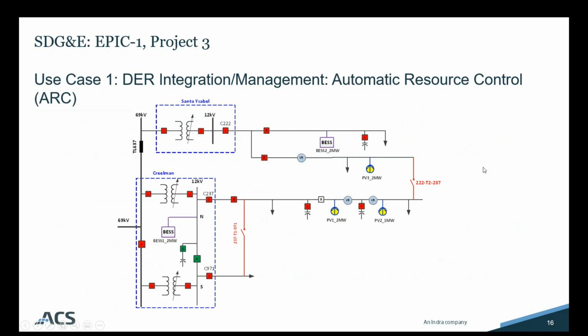So use case number one. This shows a simplified one-line diagram of the portion of the system that they wanted to simulate, and do the various test cases against and look at various scenarios. As you can see, this is composed of two different substations with two main feeders coming off of each substation. One, the Creelman substation, and the other one, the Santa Ysabel substation.